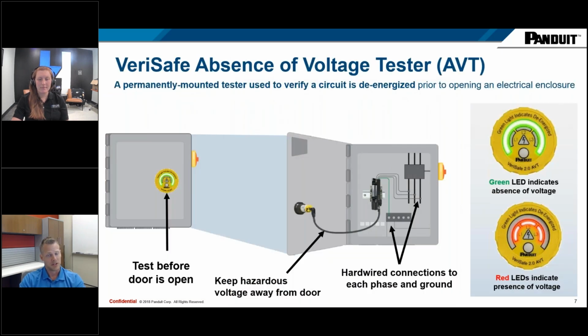Getting into absence of voltage testers, right? What are they? I've got my demo here. If we have time, I can flip my screen around or flip my camera on and show you. But it is a permanently mounted device, right? We've covered that quite a few times. And what you see here is it's typically an isolated isolation module where it's permanently installed to the voltage source. In this case, a couple of 3-phase conductors. And then the hazardous voltage is isolated at the isolation module, which is why we call it the isolation module.